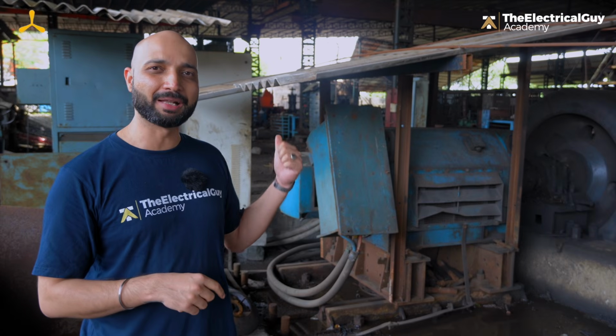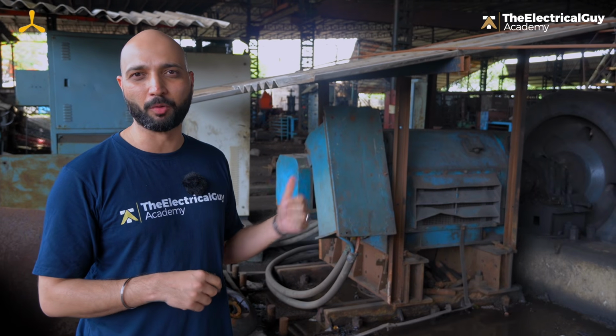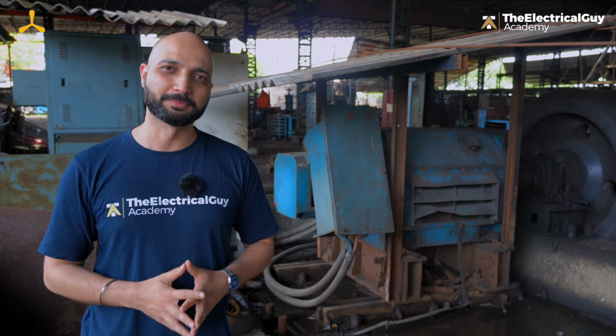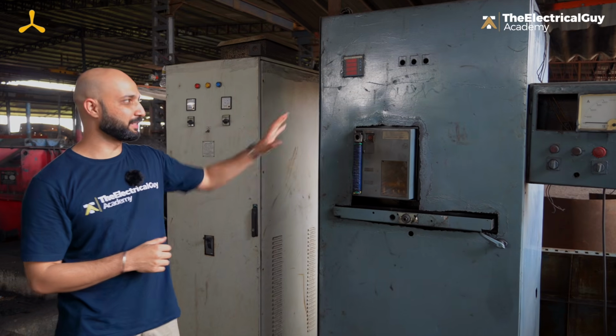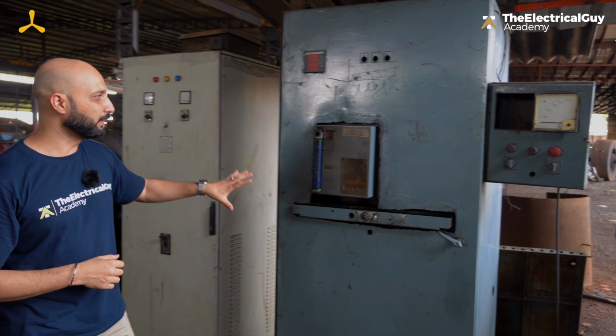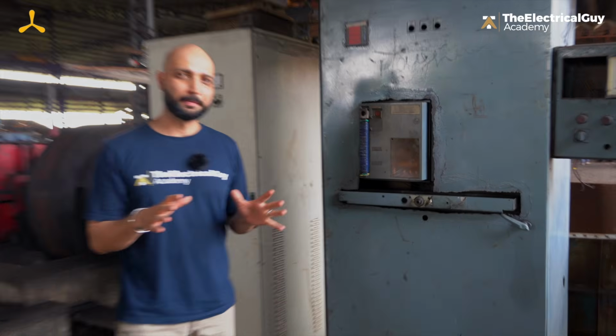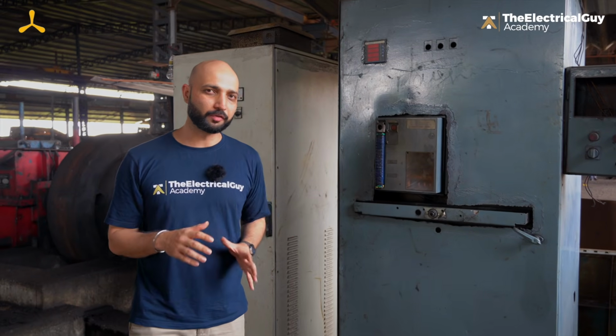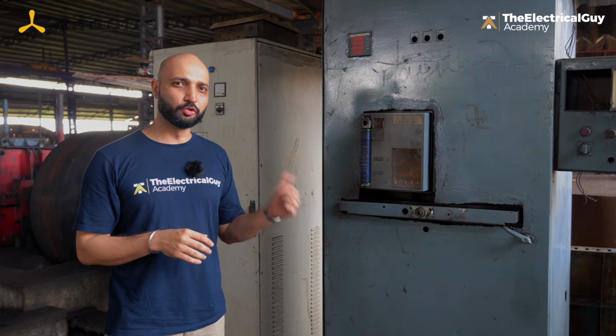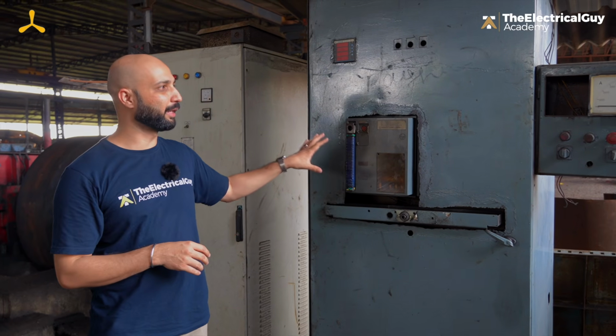I'll also show you the panel that is controlling it, the protection that is provided, so that you get full picture. Now we just saw the special duty motor, 1000 HP motor, and this is the panel that controls it. Now you see it only has a circuit breaker because we are not controlling the speed of that. We are just turning it on and turning it off. So there will not be any VFDs used for this. So this is the simple circuit breaker that you can see.